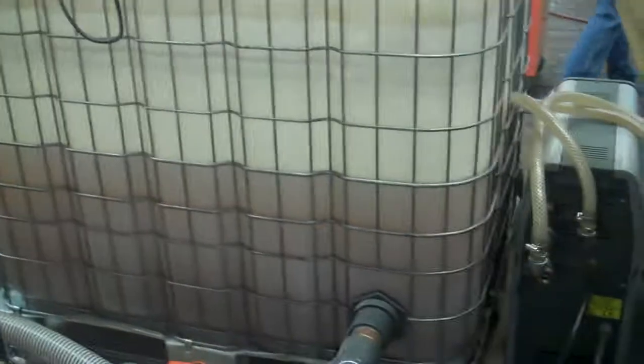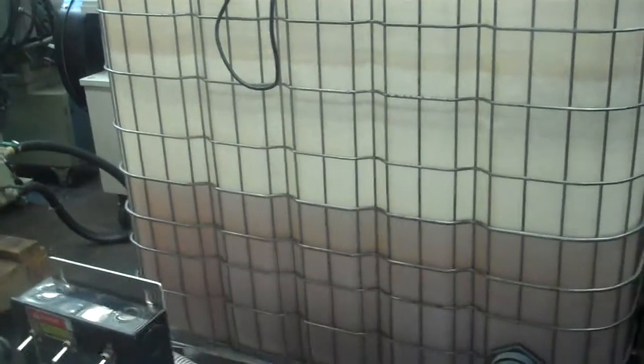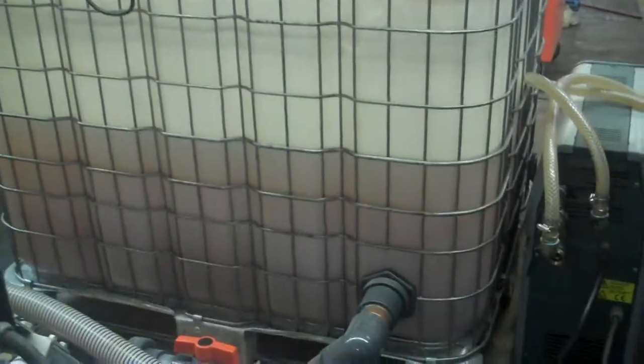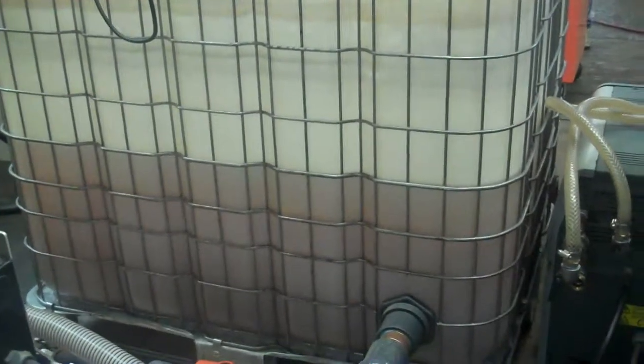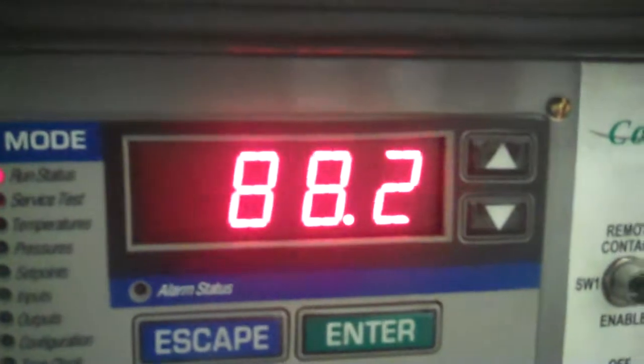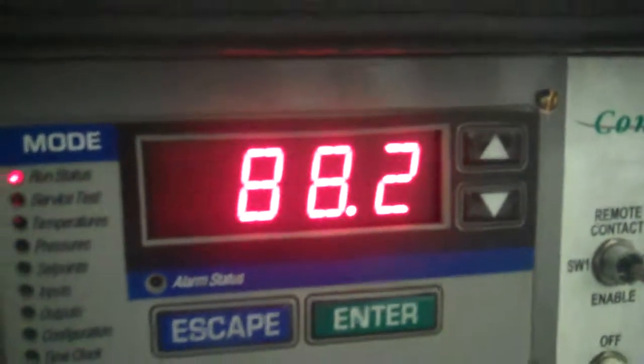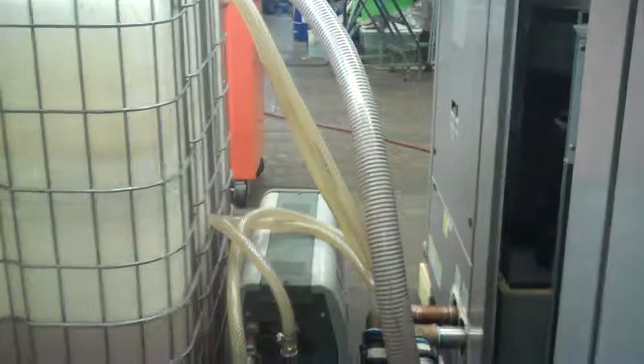We're going to be running this with a heated tank assembly here. Our test station probably heated up maybe 125 or so gallons of fluid, in this case, a glycol mix. It's at about 88 degrees or so right now, in fact, about 88.2. And we're going to chill down to about 42 degrees. We're not using our pumps here because we're going to utilize the pumps in the chiller itself. So we'll come back with video number 2 for a second.